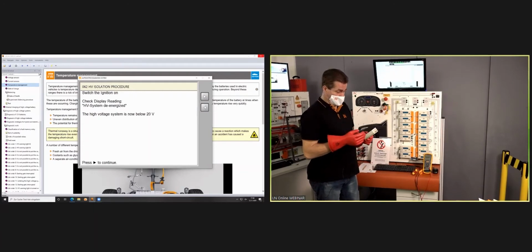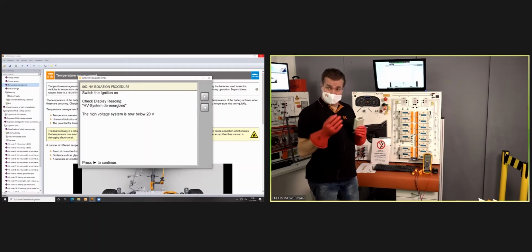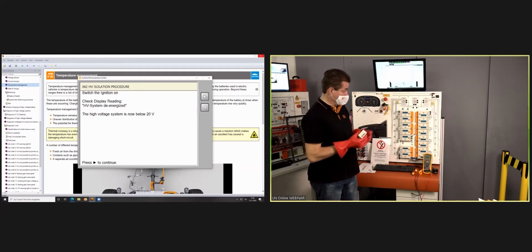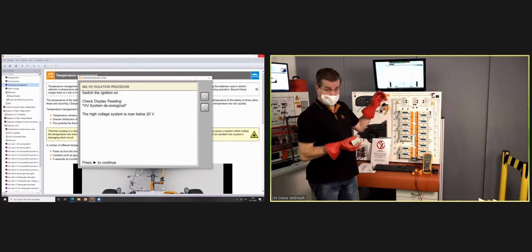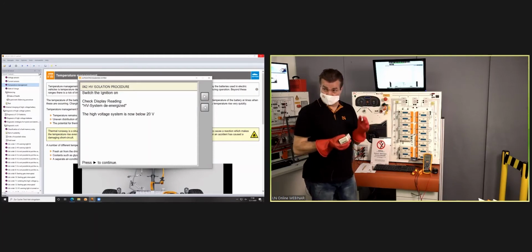In this case, there can be tiny differences between each cell over time - when we stopped we had 0.9, and now it's gone to 0.4. This tiny difference isn't a problem, but when the difference is more than 100 millivolts, it can be a problem. This is the reason why we balance.